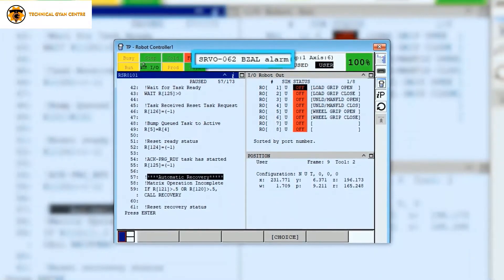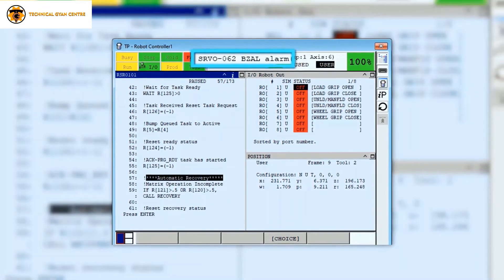If these batteries get drained, we get alarm SRVO-062 BZAL on the screen. That means we need to replace the batteries.